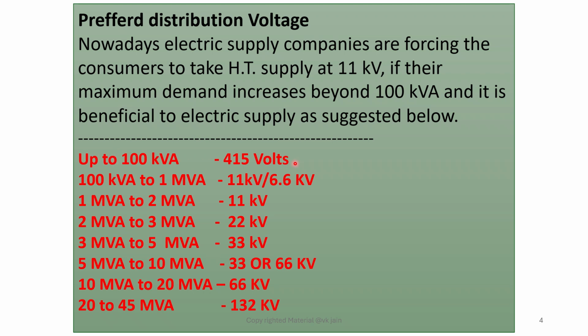Up to 100 kVA, 415 volts, 3 phase. These are all 3-phase voltages. 100 kVA to 1 MVA, you may use 11 kV or 6.6 kV systems. Then 1 MVA to 2 MVA, 11 kV; 2 to 3 MVA, 22 kV, which is used in the metro system. 3 MVA to 5 MVA, 33 kV substations of large premises. 5 to 10 MVA, 33 or 66 kV. Then 10 MVA to 20 MVA, 66 kV system, and 20 to 45 MVA, 132 kV.